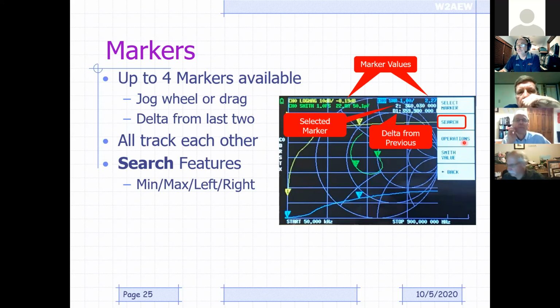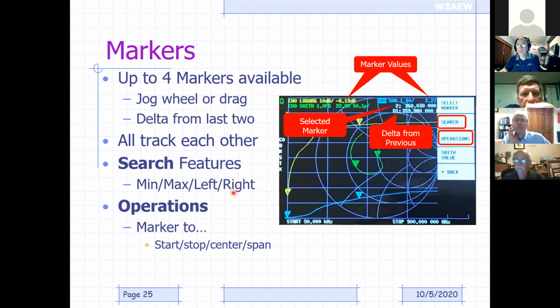There are search features for the markers to allow you to search for the min and max, or just go left and right to the next min and the next max. And there are operations that allow you to say, I want to take where this marker is in frequency and make that the new center frequency for my measurement. So the operations allow you to set the start, stop, center, or span based on marker position. These are typical features that you have in a spectrum analyzer, for example.